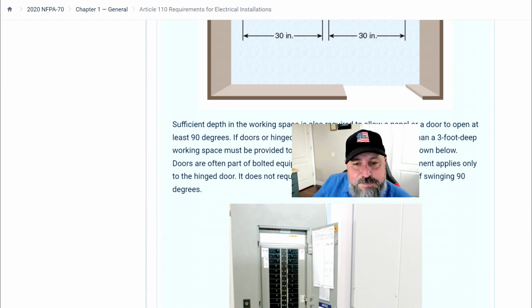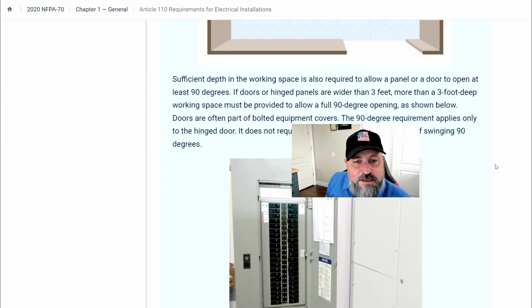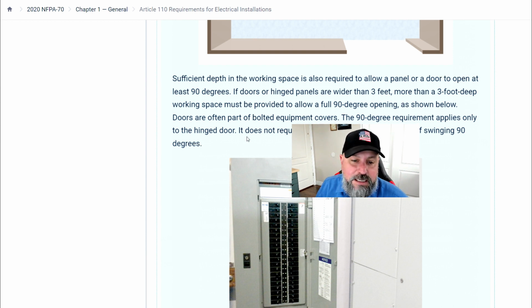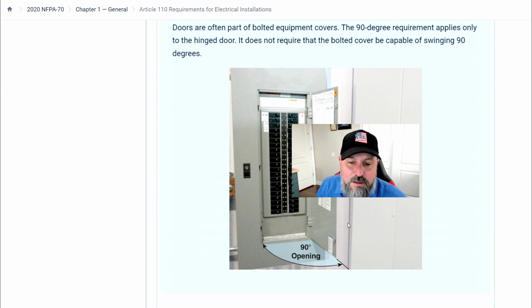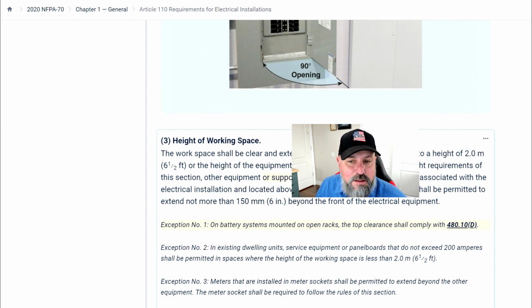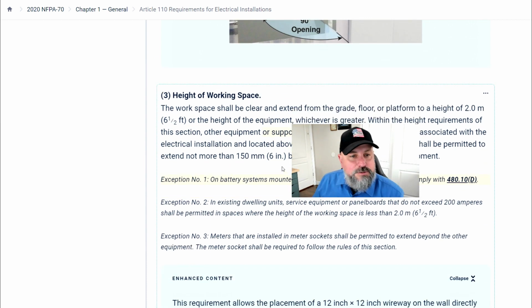Sufficient depth in the working space is also required to allow a panel or door to open at least 90 degrees. If doors or hinged panels are wider than 3 feet, more than a 3-foot deep working space must be provided to allow a full 90-degree opening, as shown below. Doors are often part of bolted equipment covers. The 90-degree requirement applies only to the hinged doors. It does not require that the bolted covers be capable of swinging 90 degrees. So when you have a door, you have to be able to open it 90 degrees, or that's going to be a violation. So this is the next one I wanted to go into, the height of the working space.